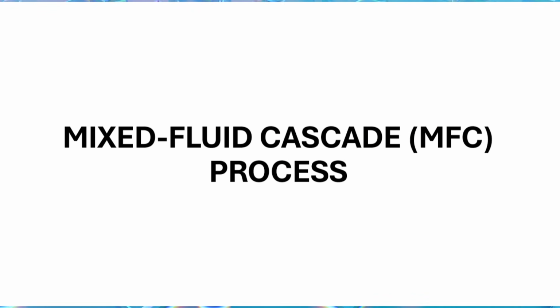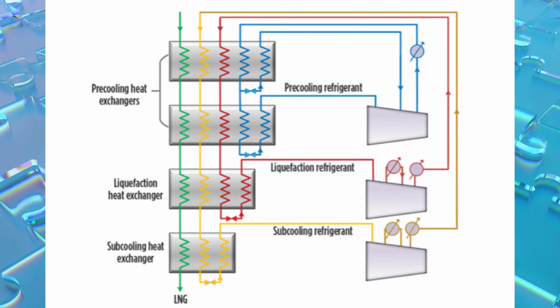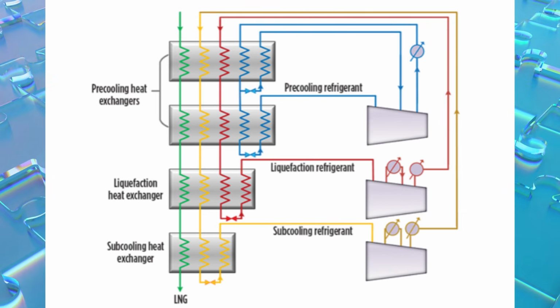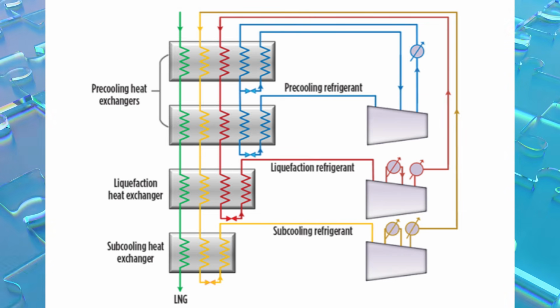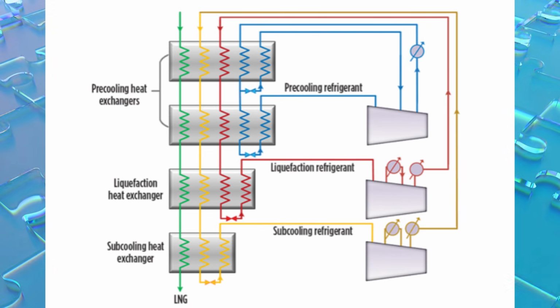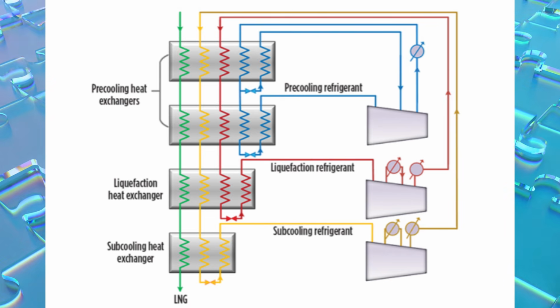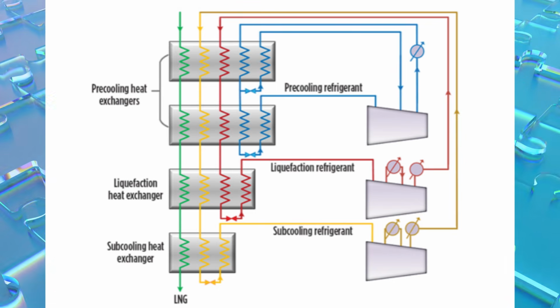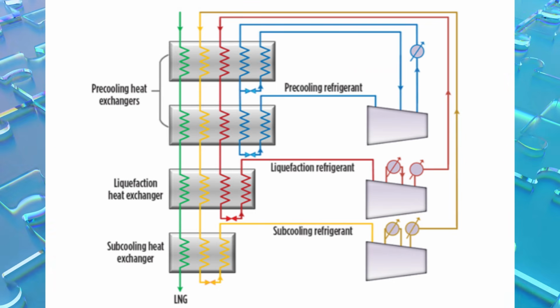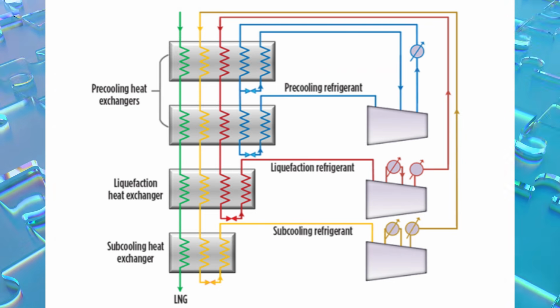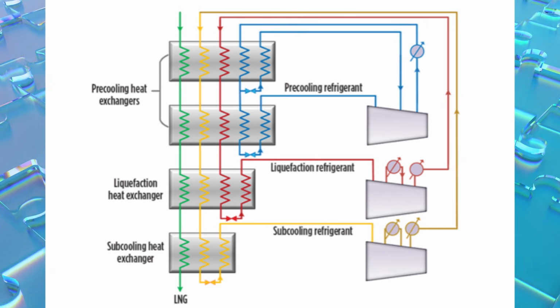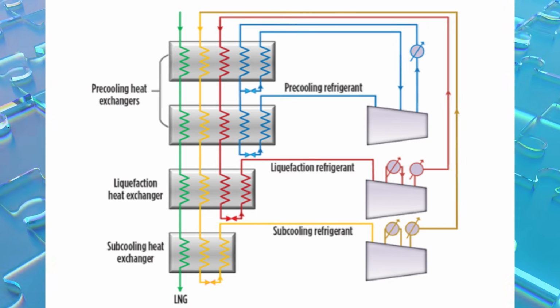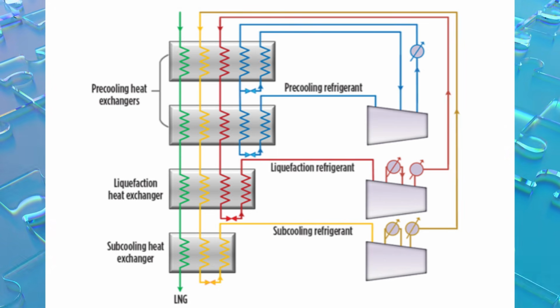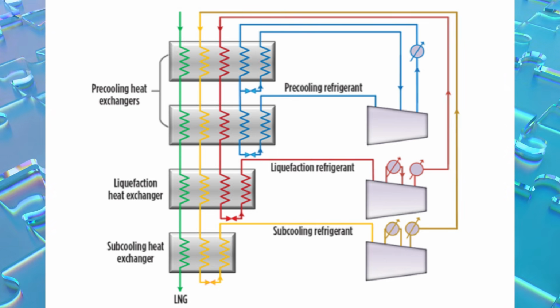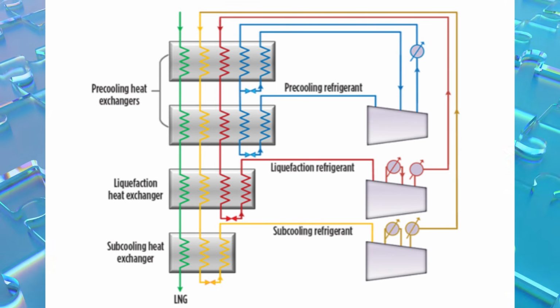In the MFC process, 3 mixed refrigerants are used to execute the pre-cooling, liquefaction, and subcooling steps. A multi-stream heat exchanger arrangement is used for the 3 cycles. In the pre-cooling cycle, the natural gas stream, liquefaction, and subcooling refrigerant are cooled to approximately -50 degrees Celsius. Both the natural gas stream and the subcooling stage mixed refrigerant are cooled during the liquefaction cycle. A typical MFC process flow diagram is shown in the slide.